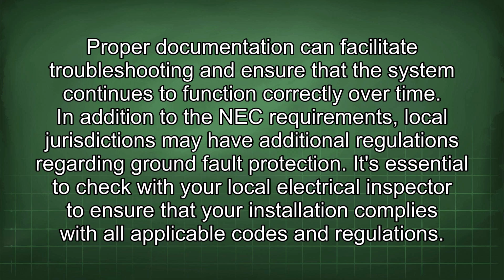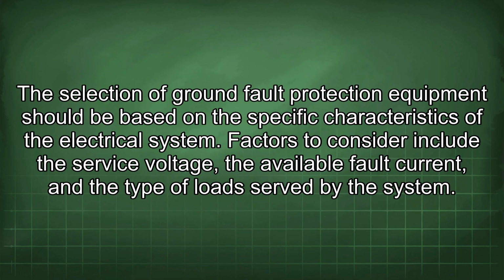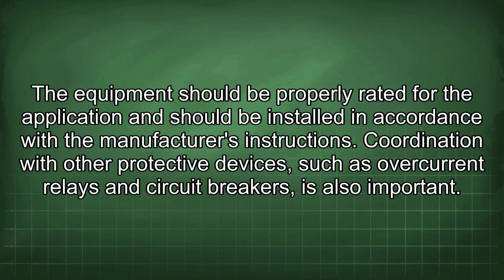In addition to the NEC requirements, local jurisdictions may have additional regulations regarding ground fault protection. It's essential to check with your local electrical inspector to ensure that your installation complies with all applicable codes and regulations. The selection of ground fault protection equipment should be based on the specific characteristics of the electrical system. Factors to consider include the service voltage, the available fault current, and the type of load served by the system. The equipment should be properly rated for the application and should be installed in accordance with the manufacturer's instructions.